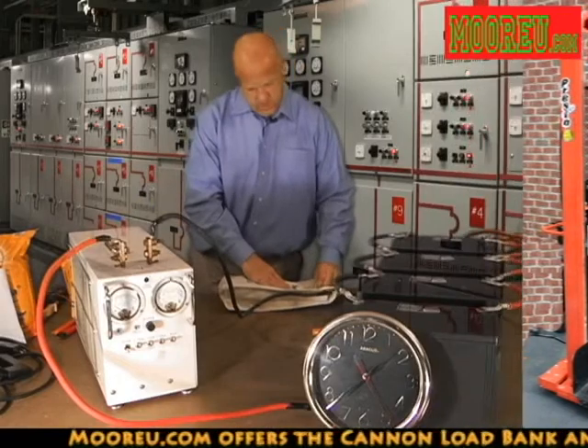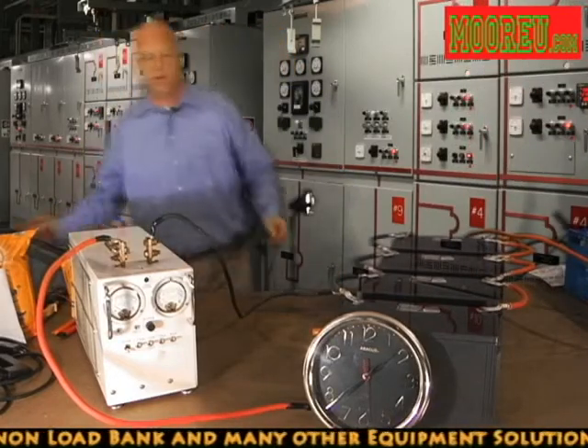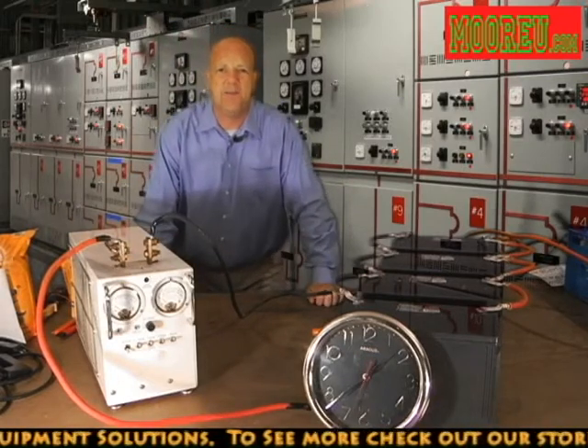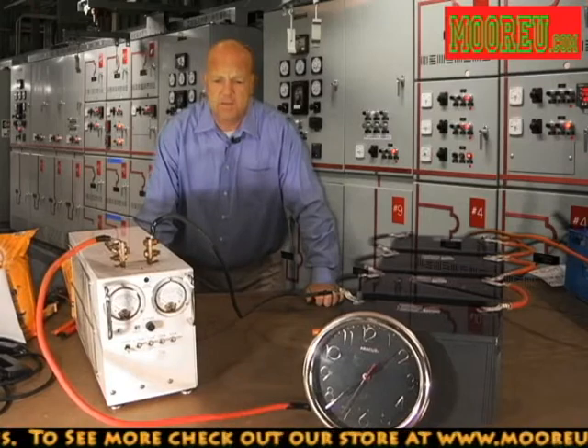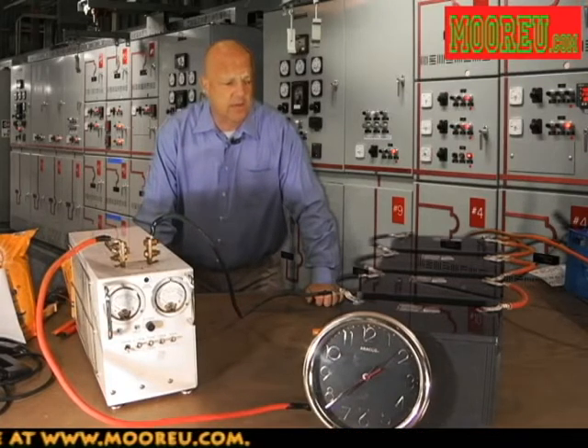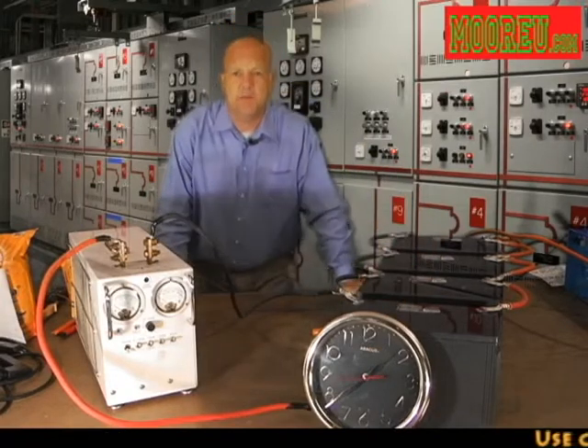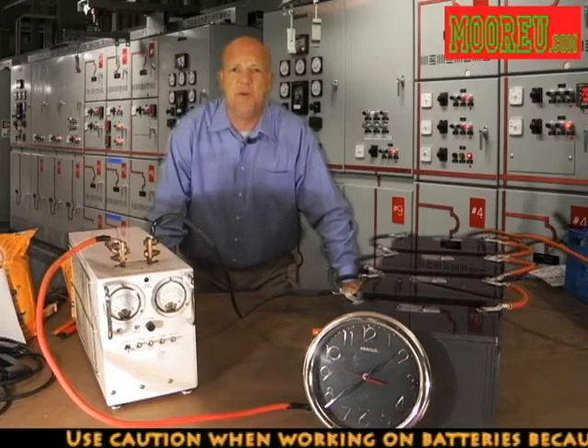For today's discharge, we're going to be using a 48-volt load bank. This is the Cannon Model L48500. This is a resistive load bank that can go up to as high as 500 amps, and it is meant for a 48-volt voltage. So what we're going to do today is take these four 12-volt monoblocks, connect them in series, and then connect it to the load bank. We'll see how well it does at the published five-minute rate.